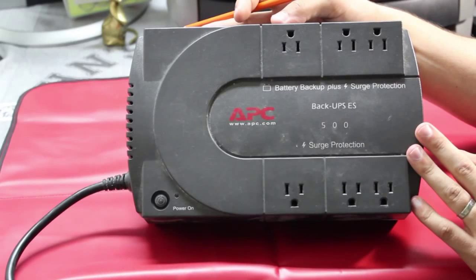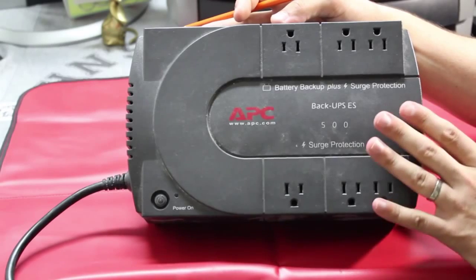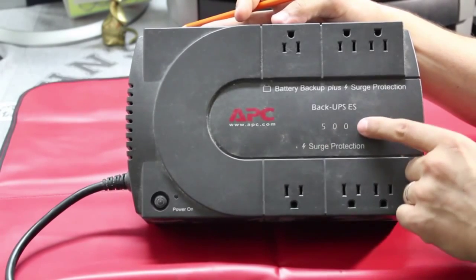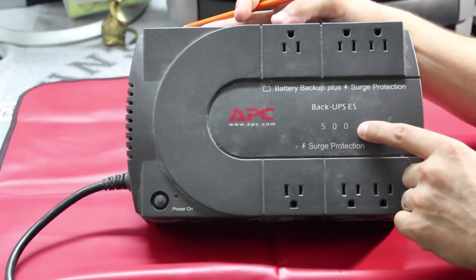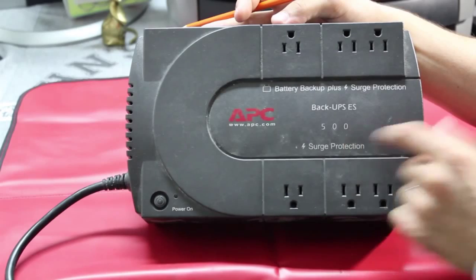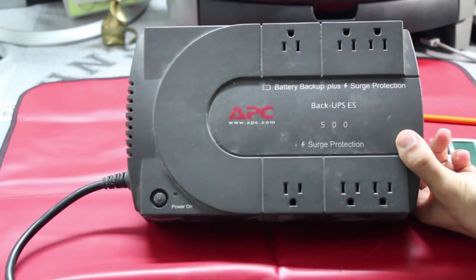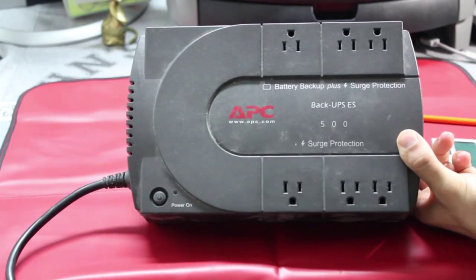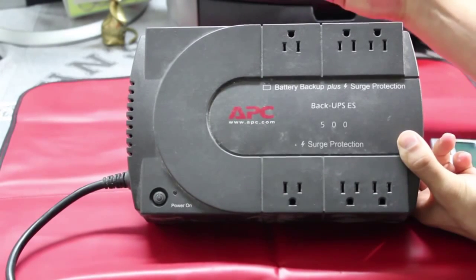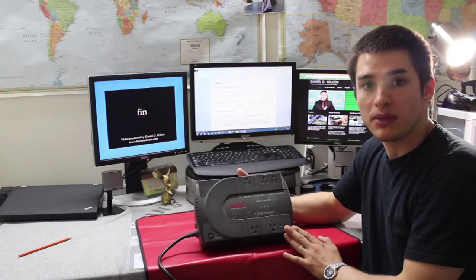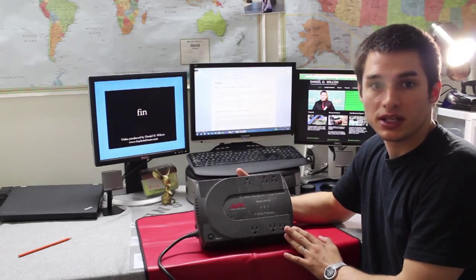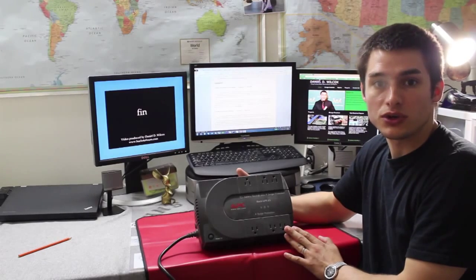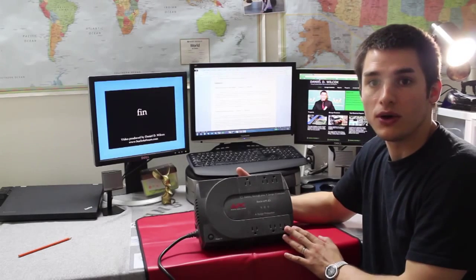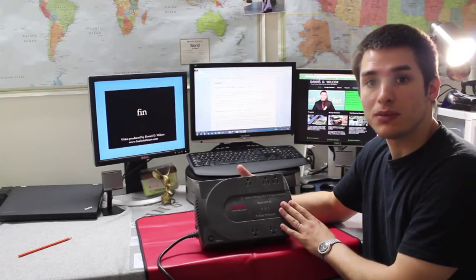The de facto standard in trying to figure out how to pick the correct UPS, if they give you the numbers in VA, is to simply take 60% of that. So multiply 500 times 0.6, and what you get is 300 watts. Even if you consider the fact that your laptop may have battery power, the surge protection on this is excellent. So even if your laptop is connected to it and there's a storm, this would also protect against surges and spikes entering your laptop, which of course your battery is not going to protect against. So this is something small that I have connected even to my laptop.